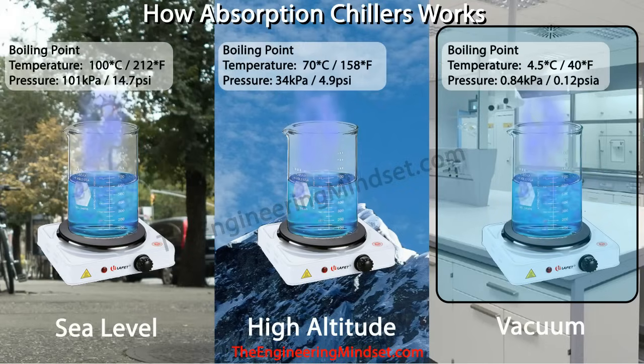If we went higher up into the atmosphere, say to the top of Mount Everest where the atmosphere is much thinner, water would boil at around 70 degrees Celsius — 158 degrees Fahrenheit — because the atmospheric pressure is only around 34 kPa or 4.9 psi. In the absorption chiller, the evaporator and absorber chamber operate at a very low pressure, almost near vacuum — about 0.84 kPa or 0.12 psia. At that pressure, water will boil at around 4.5 degrees Celsius or 40 degrees Fahrenheit.